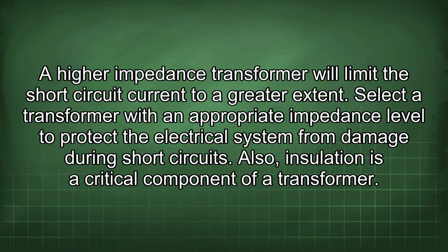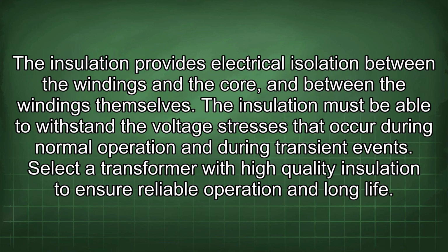Also, insulation is a critical component of a transformer. The insulation provides electrical isolation between the windings and the core, and between the windings themselves. The insulation must be able to withstand the voltage stresses that occur during normal operation and during transient events. Select a transformer with high-quality insulation to ensure reliable operation and long life.